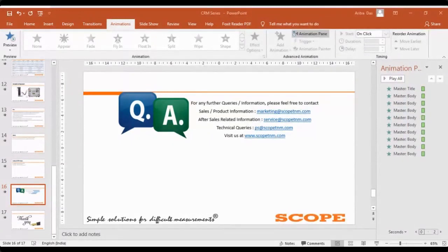Yeah. So the basic Kelvin's bridge that we learned during our college days, this is the extension. This CRM product has been developed based on that basic principle, sir. The bridge balancing is done automatically with the help of electronics, and the 4-wire method, as Aritra explained, means we do not have to do lead resistance compensation. So that's the basic reason for using the 4-wire method.